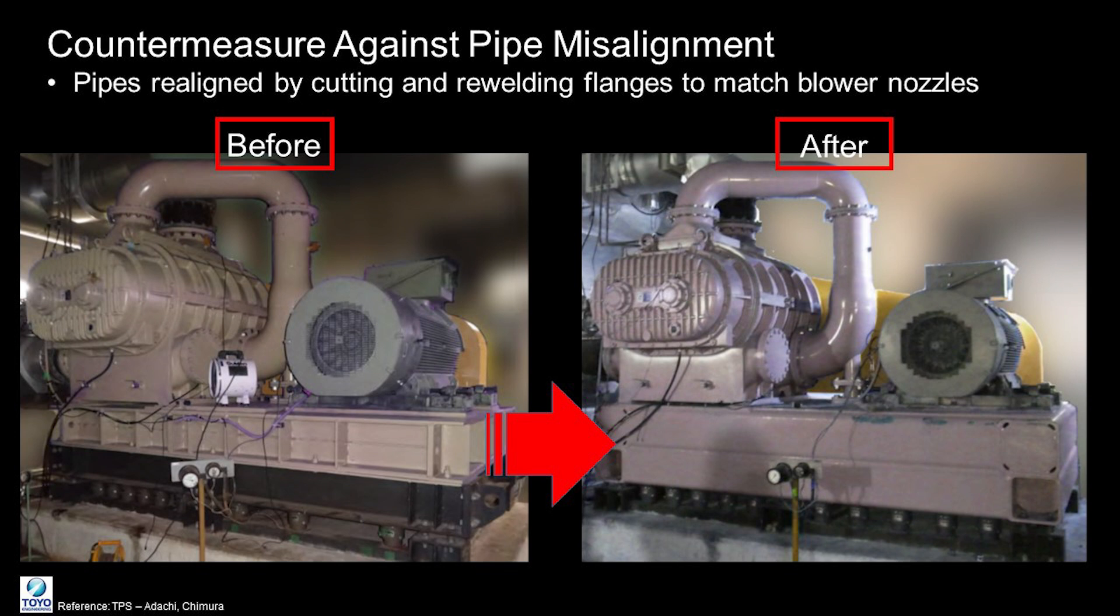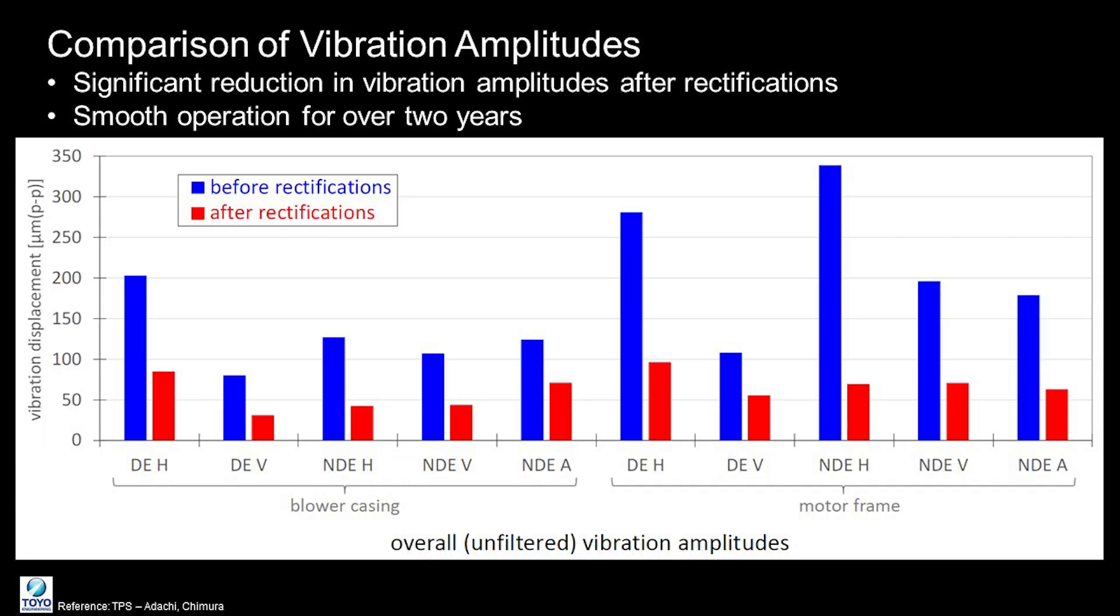After implementing the base plate rectification and pipe realignment, large reductions in vibration amplitude were measured throughout the equipment. The system has been running smoothly without issues for many years after these fixes.